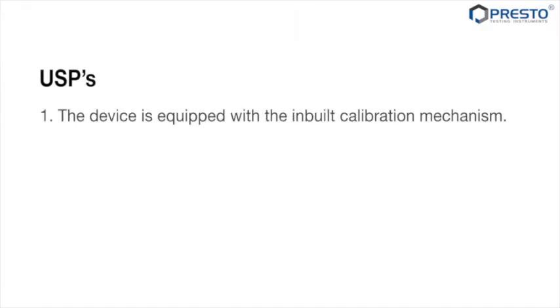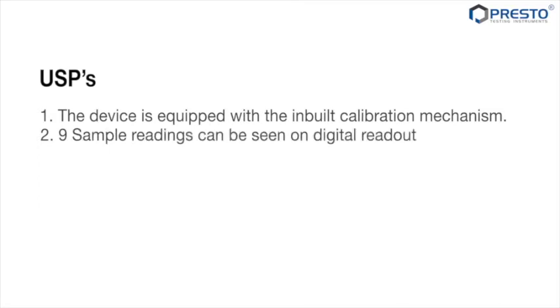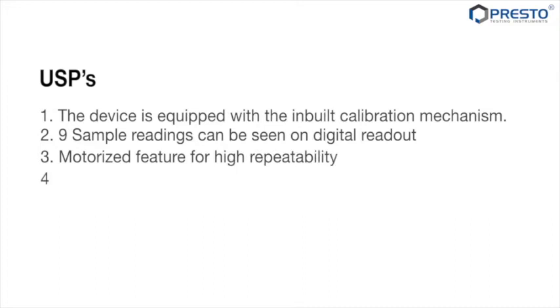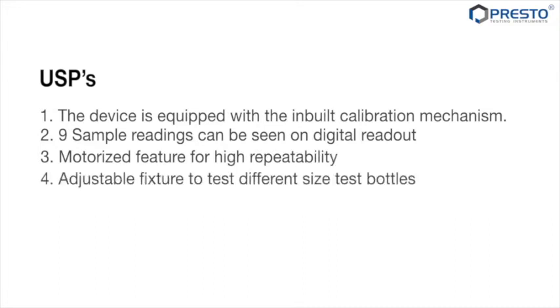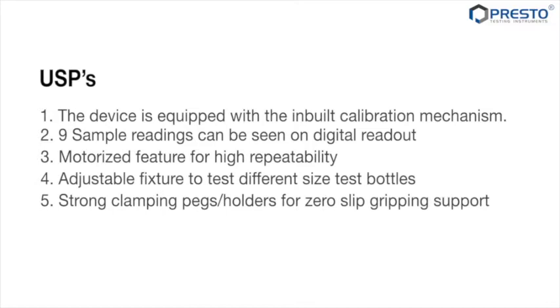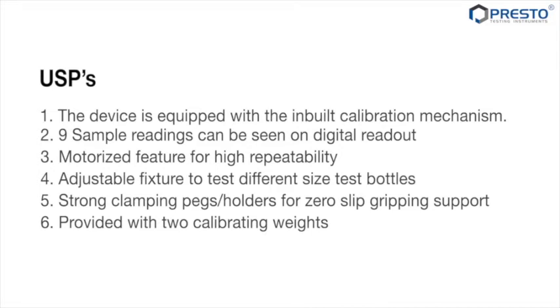USPs. The device is equipped with the inbuilt calibration mechanism. 9 sample readings can be seen on digital readout. Motorized feature for high repeatability. Adjustable fixture to test different sizes of test bottles. Strong clamping pegs holders for zero slippage support, provided with 2 calibrating weights. Other standard technical specifications.